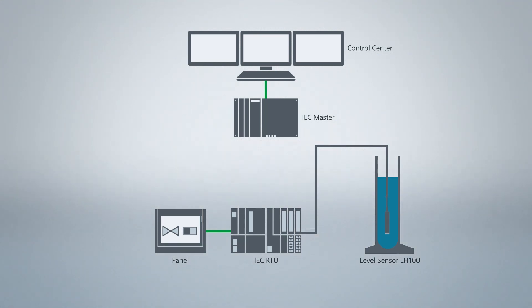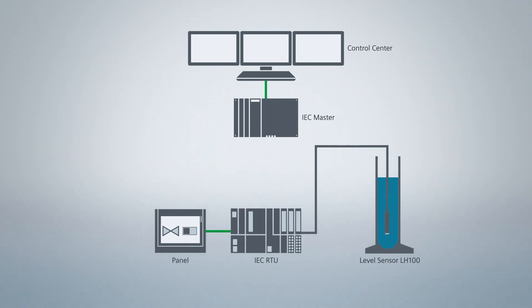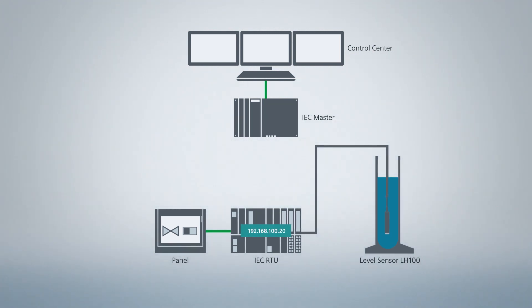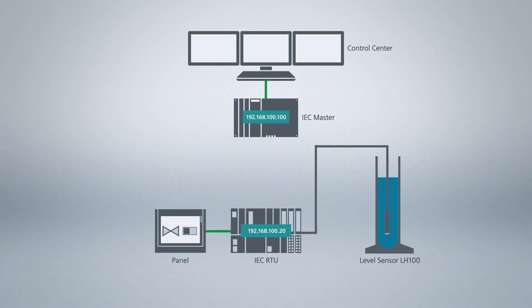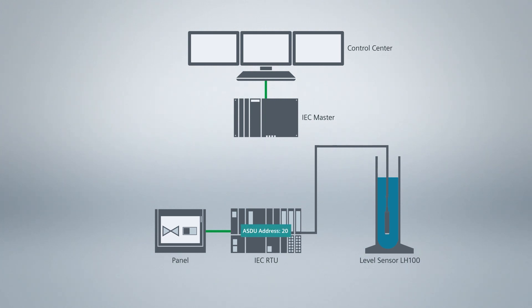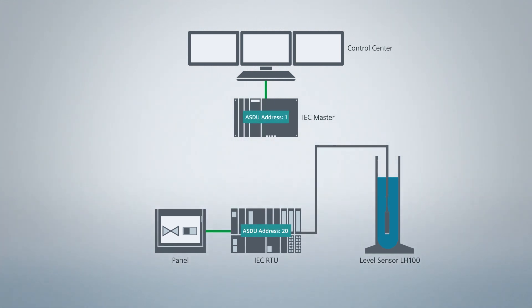As control system, a WinCC telecontrol project with IEC 60870 driver is pre-configured. The ET200SP RTU has the IP address 192.168.100.20. The IEC master has the IP address 192.168.100.100. As IEC address, also called ASDU, I use address 20 for the RTU. The IEC master operates under IEC address 1.